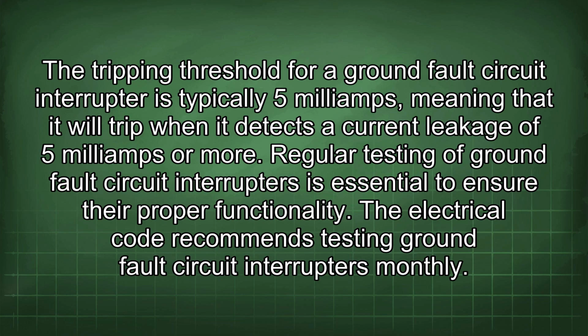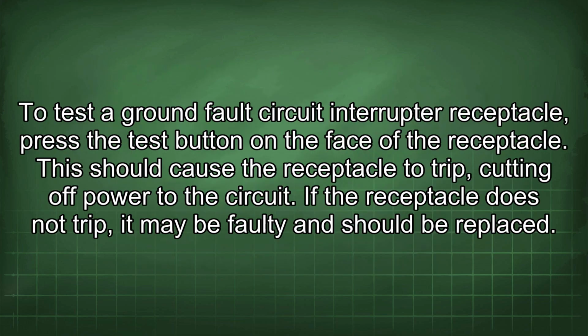The electrical code recommends testing ground fault circuit interrupters monthly. To test a ground fault circuit interrupter receptacle, press the test button on the face of the receptacle. This should cause the receptacle to trip, cutting off power to the circuit. If the receptacle does not trip, it may be faulty and should be replaced.